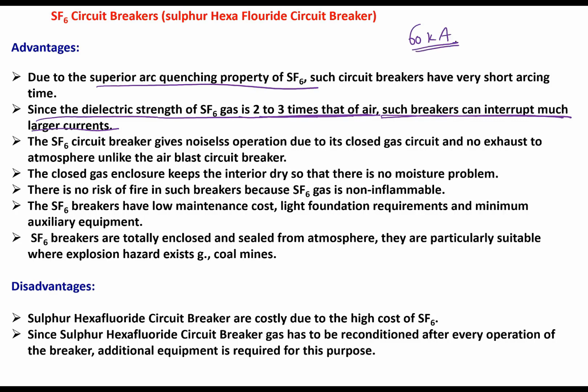Understand? It gives noiseless operation due to its closed gas circuit and no exhaust to atmosphere like the air blast circuit breaker. So it is noise free, it will not give any exhaust. In an air blast circuit breaker, the high pressure gas after use has to be released to atmospheric pressure. But here it is a closed loop gas circuit, so no exhaust is obtained. No moisture problem. The closed enclosure keeps the interior dry, so there is no moisture problem.